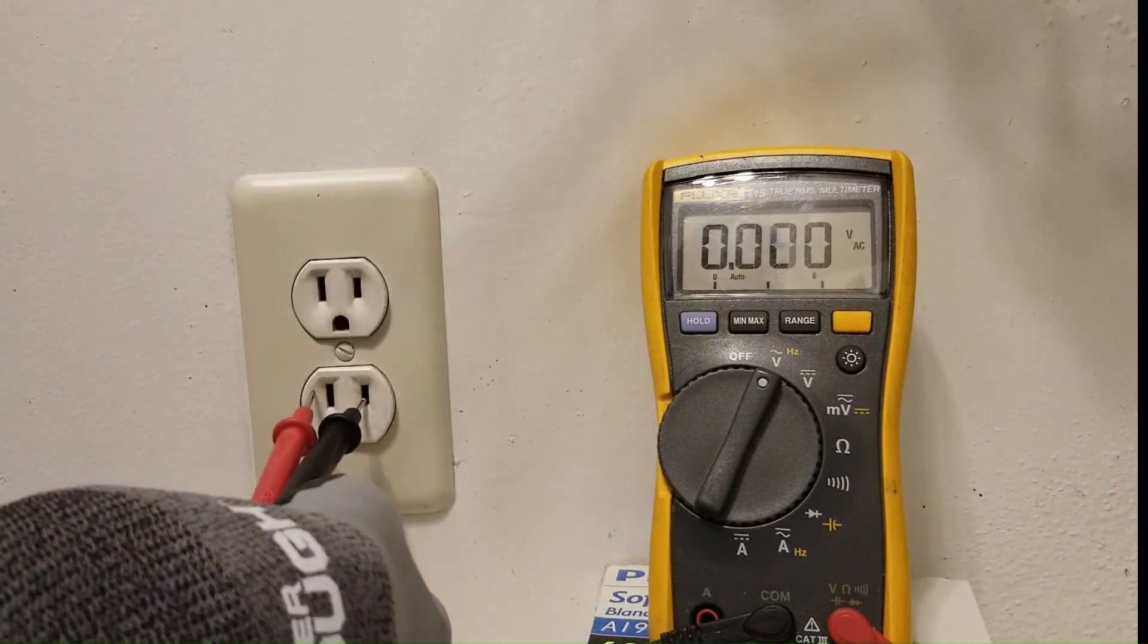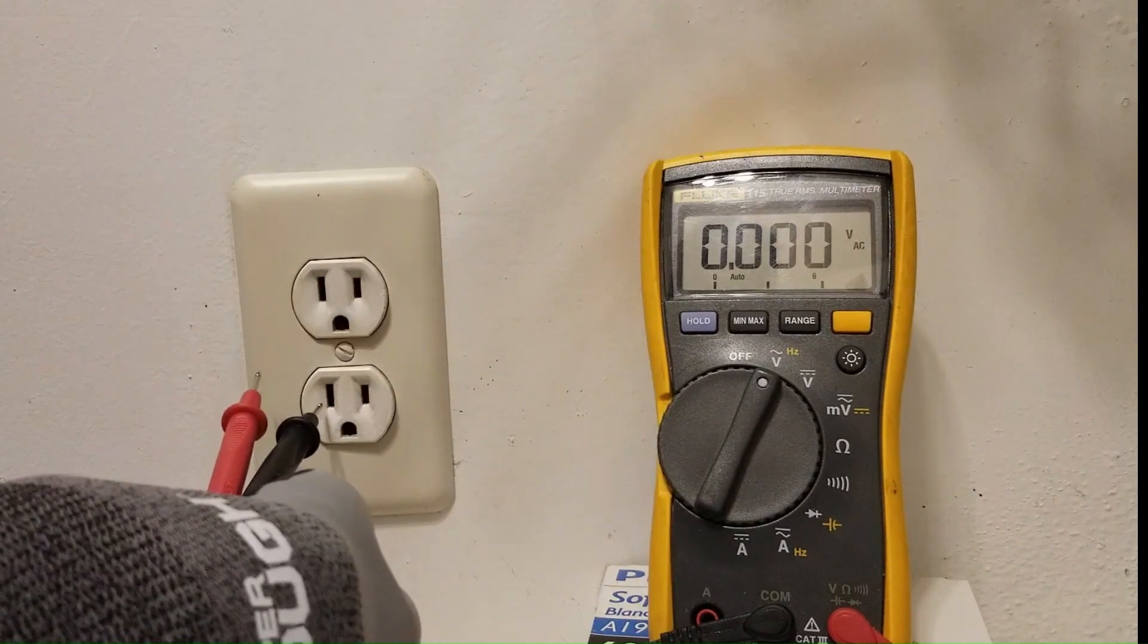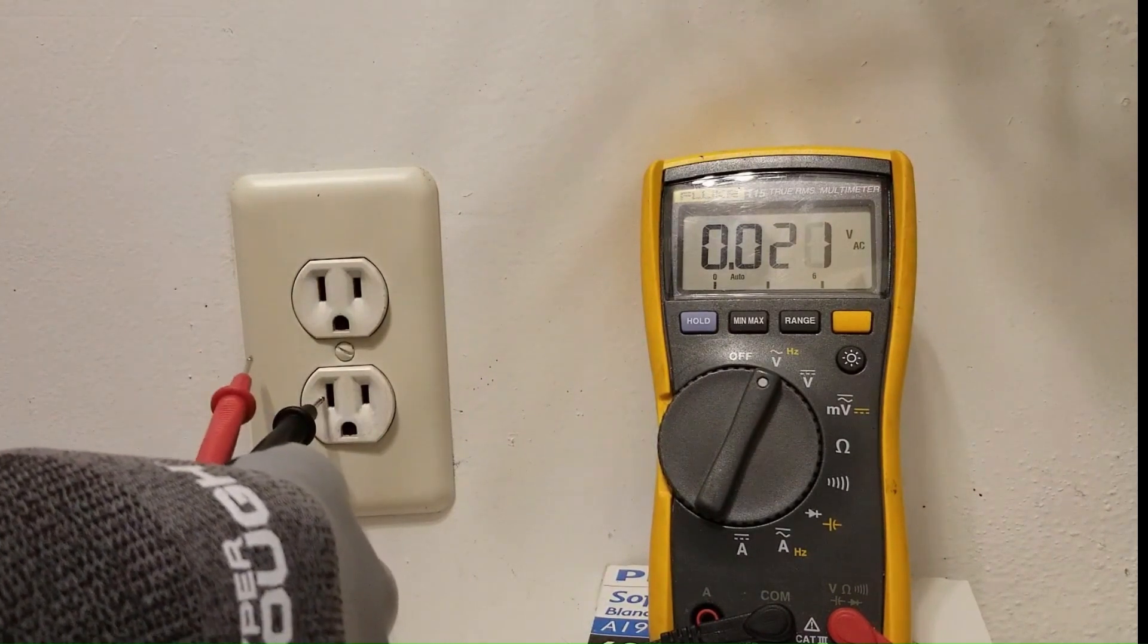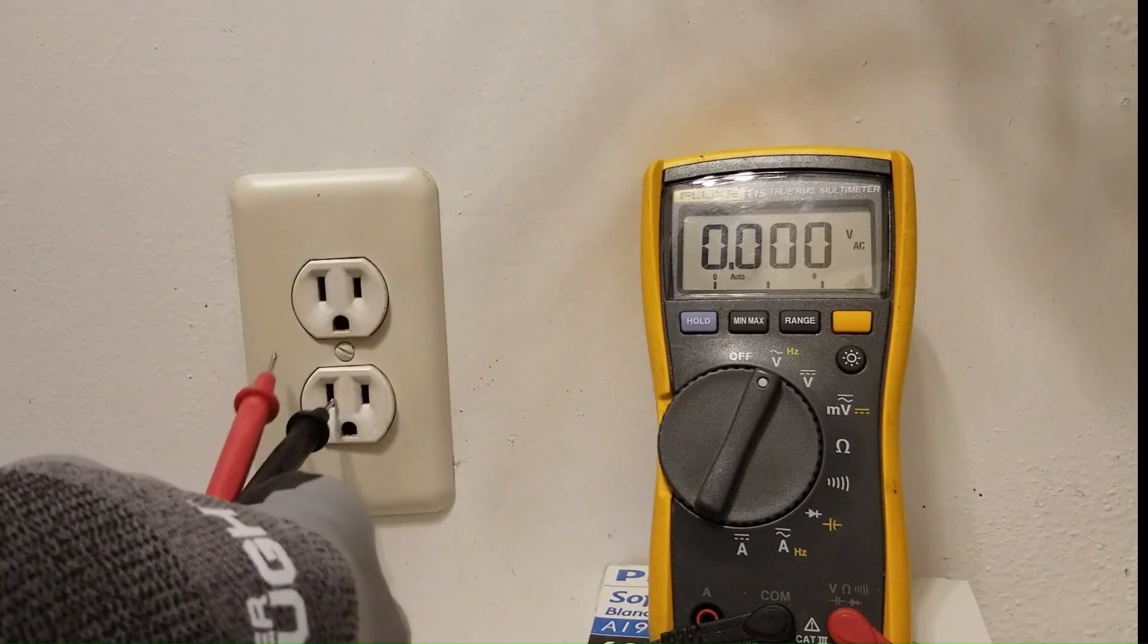So if you only have a couple of volts across here that means that hot is around 120 with respect to ground. That means neutral is around 118 with respect to ground. So neutral is being pulled up because there's a loose upstream connection.